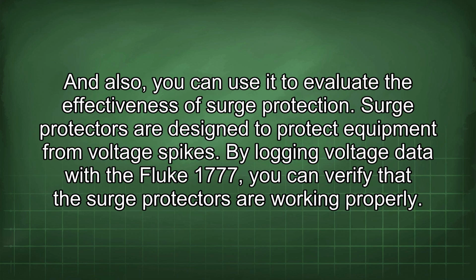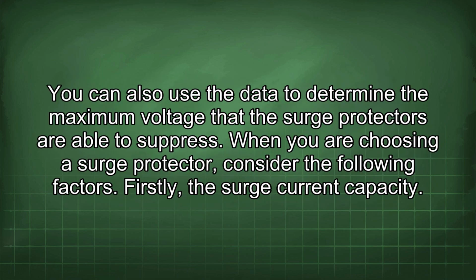And also, you can use it to evaluate the effectiveness of surge protection. Surge protectors are designed to protect equipment from voltage spikes. By logging voltage data with the Fluke 1777, you can verify that the surge protectors are working properly. You can also use the data to determine the maximum voltage that the surge protectors are able to suppress.